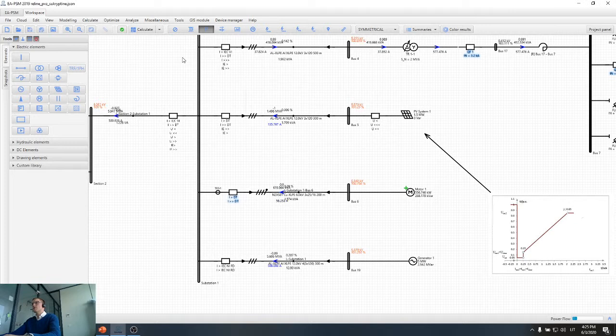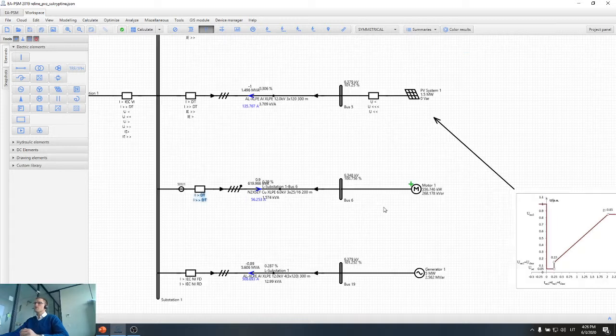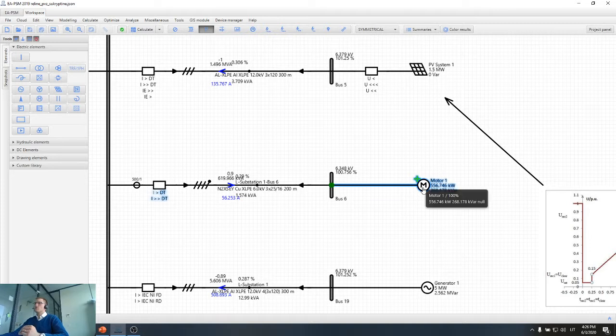What we would like to do as well, maybe, is add under voltage relays for our motor, because let's say we have under voltage conditions during a short circuit or during other motor startings, so the motor speed will go down, and after the voltage gets back to normal, the motor speed can very quickly start to accelerate, and this will cause high inrush currents for the motor. So to avoid that, we might use under voltage relays.